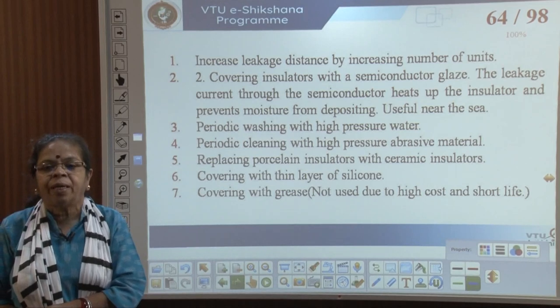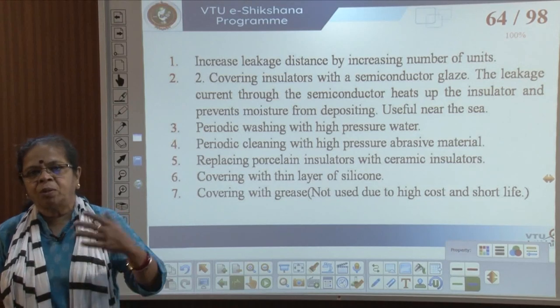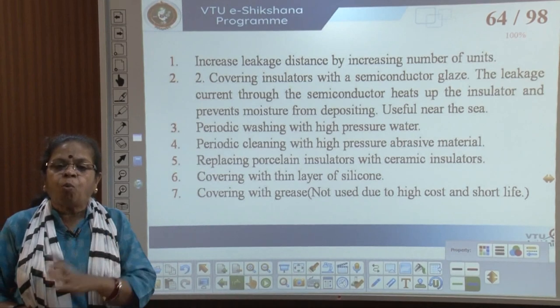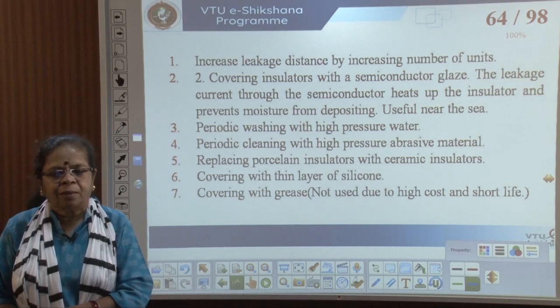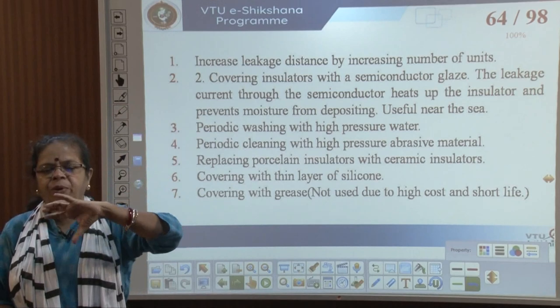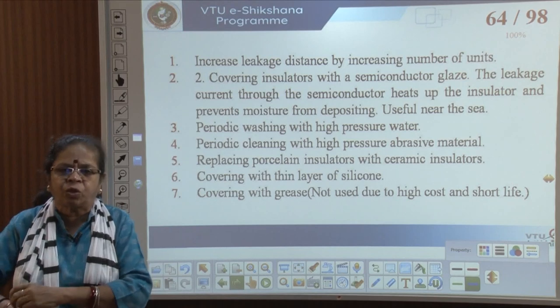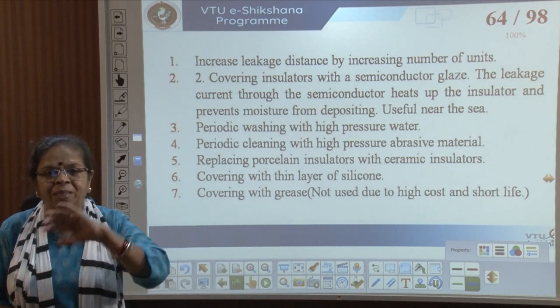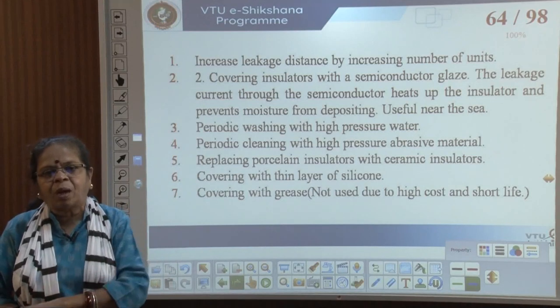The semiconductor glaze approach is very useful in places close to the sea where there is a lot of both salt and moisture. Periodic washing with high-pressure water can also be done, though it is not an easy task as it requires people to go up with high-pressure nozzles. High-pressure abrasive material can also be used to clean insulators so any deposits come off.